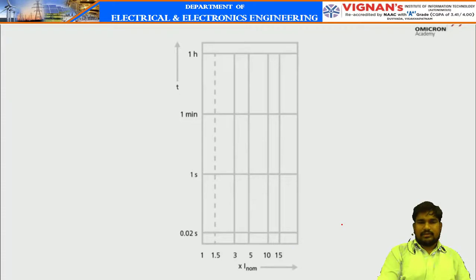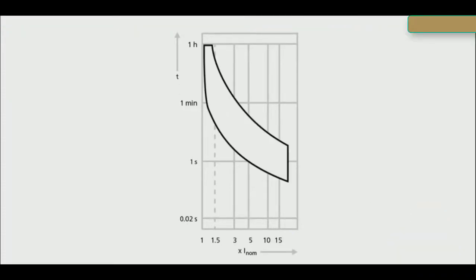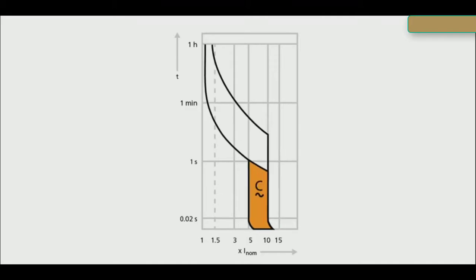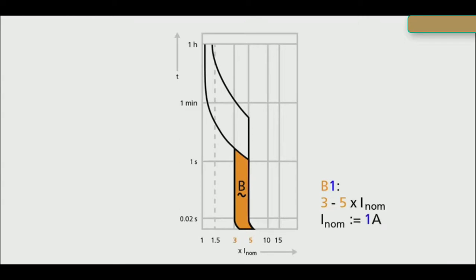If you observe, the characteristics show a thermal trigger for overloads and a magnetic trigger for short circuits. Different tripping characteristics for MCBs exist, such as D or C, with B being the type most commonly used. For instance, a B1 rating means that the MCB will instantaneously trip currents in between 3 to 5 times the nominal current, with the nominal current being 1 amp.